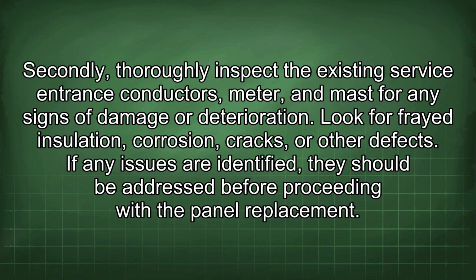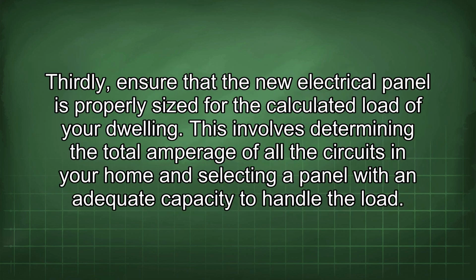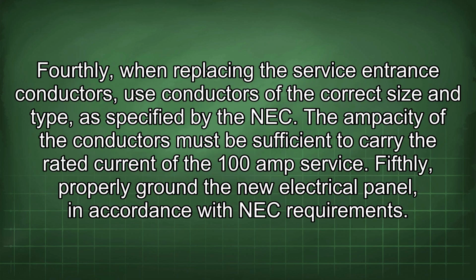Secondly, thoroughly inspect the existing service entrance conductors, meter, and mast for any signs of damage or deterioration. Look for frayed insulation, corrosion, cracks, or other defects. If any issues are identified, they should be addressed before proceeding with the panel replacement. Thirdly, ensure that the new electrical panel is properly sized for the calculated load of your dwelling. This involves determining the total amperage of all the circuits in your home and selecting a panel with an adequate capacity to handle the load. Fourthly, when replacing the service entrance conductors, use conductors of the correct size and type as specified by the NEC. The ampacity of the conductors must be sufficient to carry the rated current of the 100 amp service.